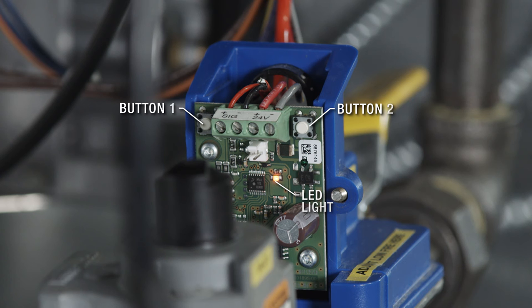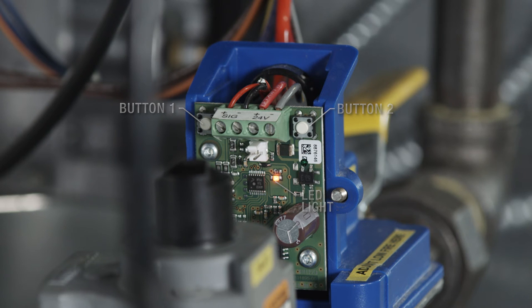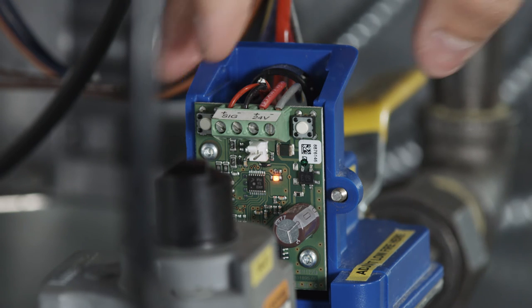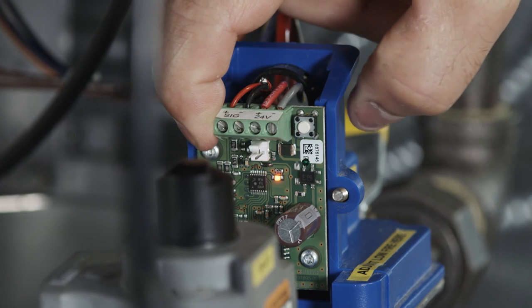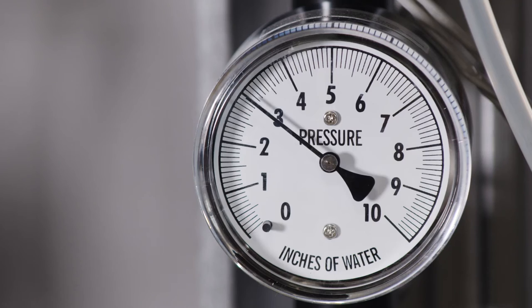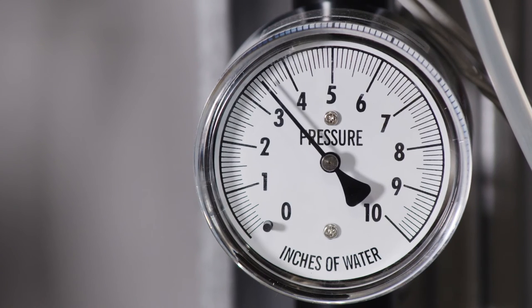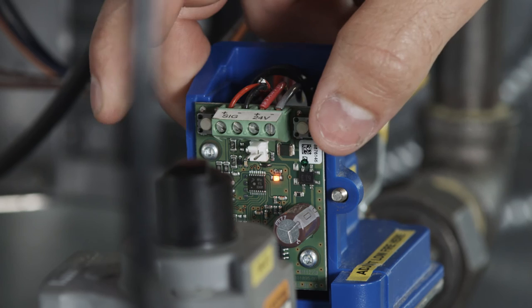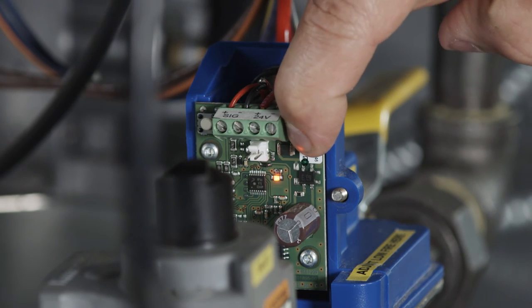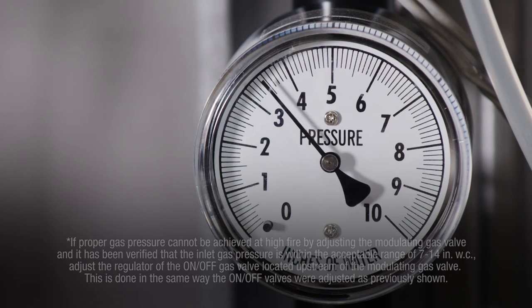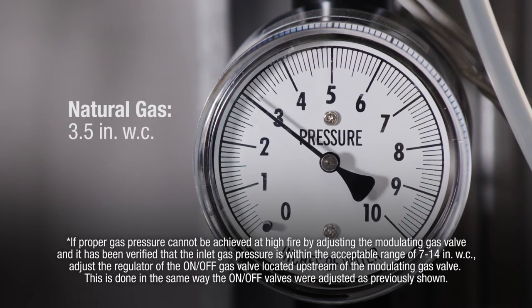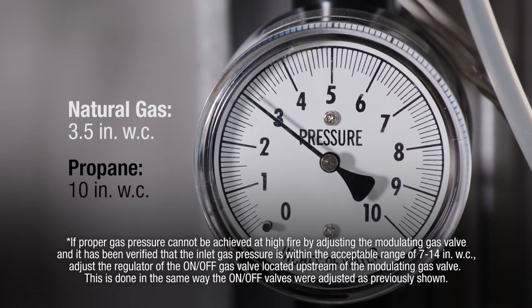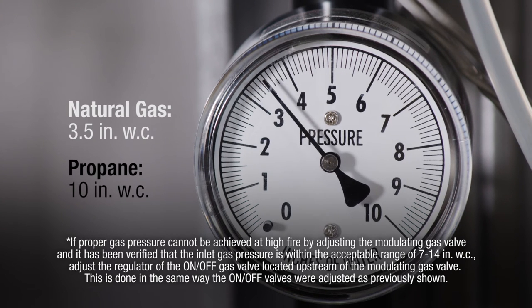Buttons 1 and 2 are now used to set desired high fire settings. Press once for slight adjustment or hold for a large adjustment. Button 1 increases pressure. Button 2 decreases pressure. While viewing the gauge, the pressure should be adjusted to equal 3.5 inches water column for natural gas and 10 inches water column for propane.